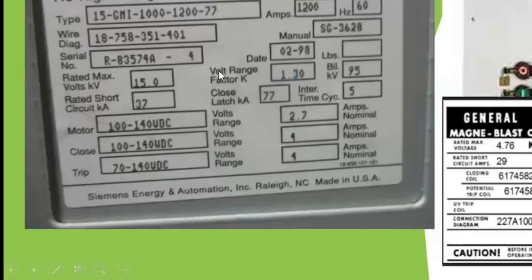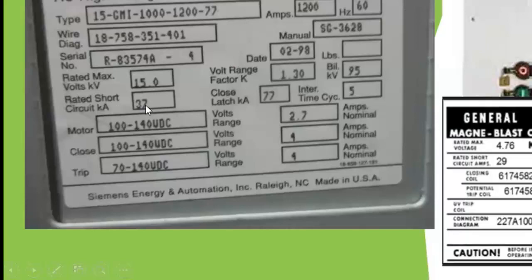The rated short circuit current is about 37 kiloamps. Your load flow calculation will tell you the maximum short circuit current in any branch of the circuit, and that informs your choice. You want to select this circuit breaker to protect a line where the short circuit current is less than this rated value, because anything beyond it can damage the breaker. Once within this rating, the breaker can handle it without damaging the contacts.